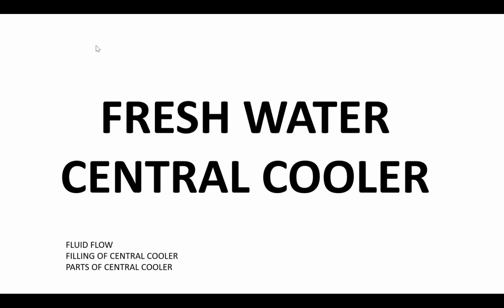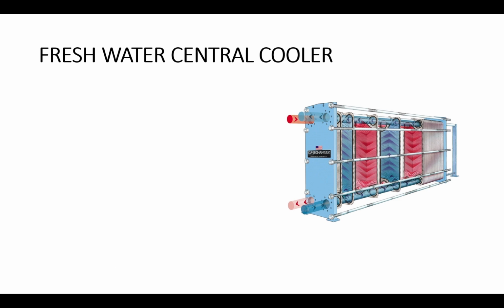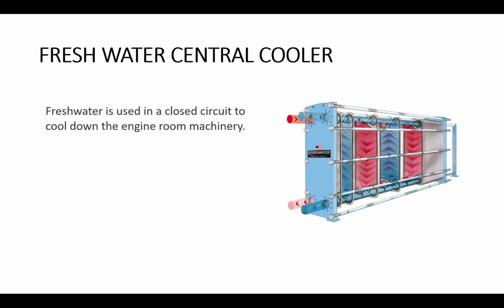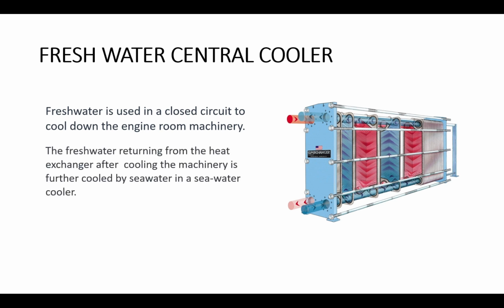Good day. We will talk about the fresh water central cooler, fluid flow, filling of the central cooler, and parts of the central cooler. What is a fresh water central cooler? Fresh water is used in a closed circuit to cool down the engine room machinery. The fresh water returning from the heat exchanger after cooling the machinery is further cooled by seawater in a seawater cooler. The central cooler consists of seawater as the cooling agent and fresh water as the fluid to be cooled.